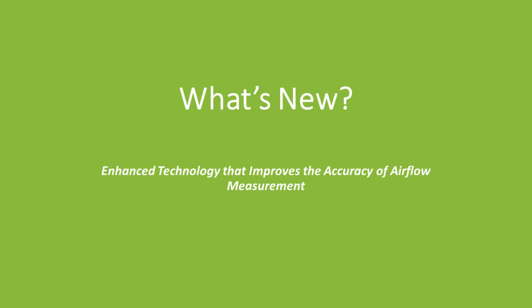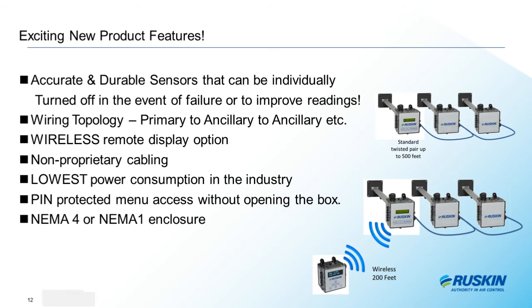We have the product that can measure and report both temperature and airflow in a more efficient and effective way than ever before. Accurate and durable sensors that can be individually turned off in the event of failure or to improve a reading. More on that in a minute. We're not wiring the probes back to a transmitter box. This exciting new product has a primary probe and almost any number of ancillary probes. The primary probe is the automation interface. Probes are connected in a daisy chain fashion, one probe to the next, using standard twisted pair wire.